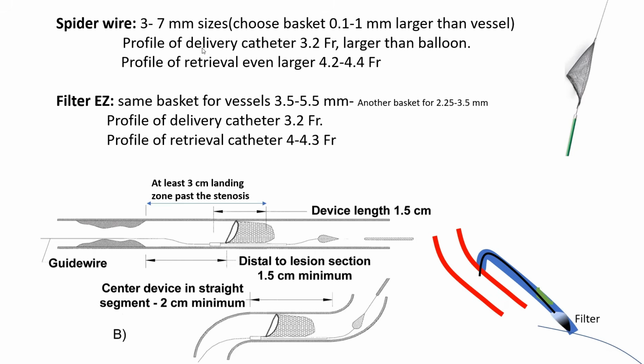The profile of the delivery catheter, that green one through which you're delivering the basket, is a 3.2 French, which is larger than the profile of a balloon. Keep that in mind. It's not easy to advance those basket catheters. The profile of the retrieval catheter through which you're pulling that basket is even larger. The whole retrieval catheter is 4.2 to 4.4 French. So you may have issues advancing the retrieval catheter even if you've properly deployed the basket. The profile of the retrieval catheter is actually larger than the profile of a modern stent, which is around 3 French.